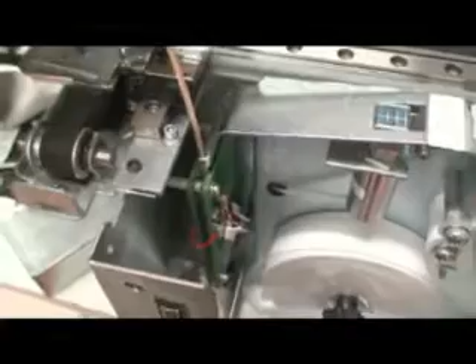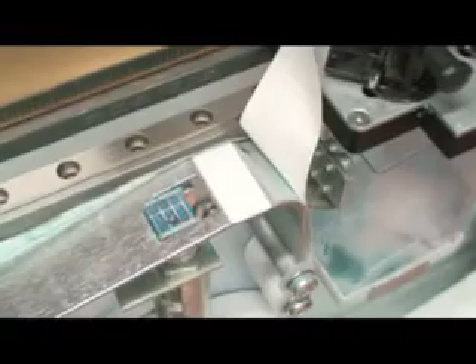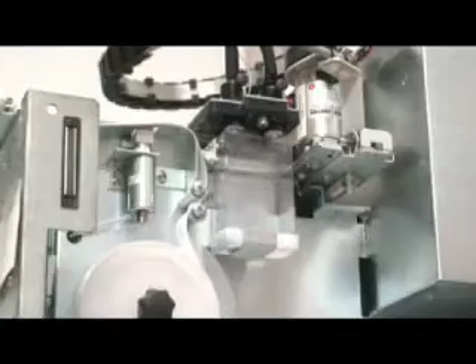While we're around this side of the machine, there's a couple of simple things to be aware of. You may have noticed there's a white sticker under the tape where the machine does its jet testing. Again, this is very important to the machine's calibration. There's a sensor on the underside of the build carriage, and prior to every jet test, this sensor reads the paper to make sure it's clean and white. The sensor can see through the paper tape, thus the sticker there to make it even whiter. This sensor also reads the crosses that the jet prints out to make sure it's running properly. I hope this tour gives you more insight into how the machine works, and in turn makes it a lot easier to run.